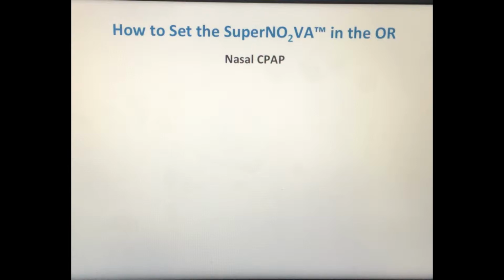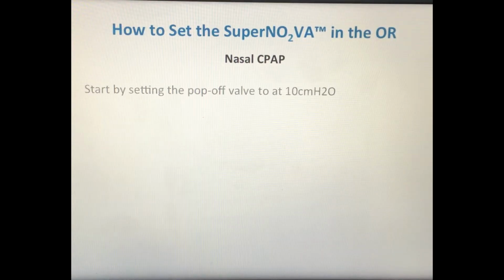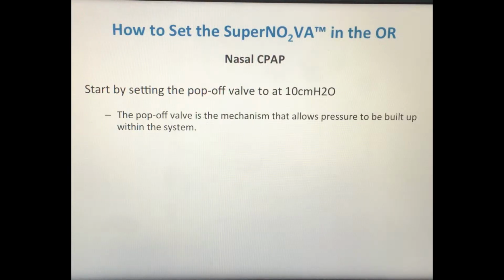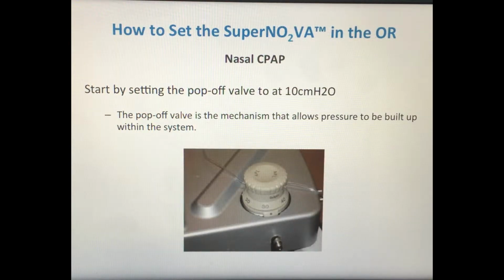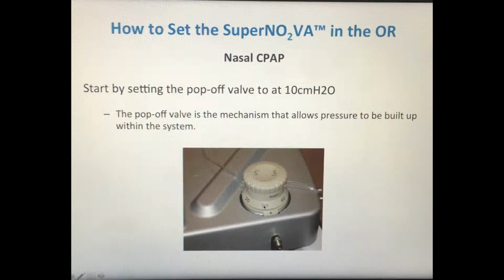Once the SuperNO2VA is tightly placed on the patient's nose, it's time to generate pressure. In order to do so, you want to recommend to the clinician to start by turning the pop-off valve to 10 centimeters of water pressure. This will allow pressure to be built up within the system. As you see here, this is the pop-off valve, and this is what you would recommend that the clinician turns, starting off at about 10 centimeters of water pressure.